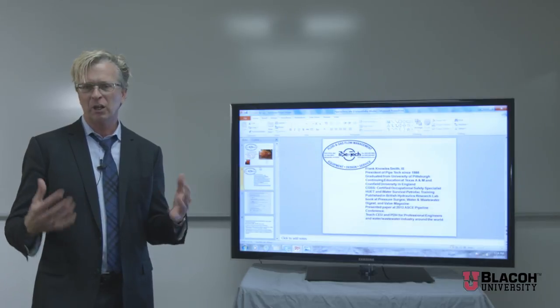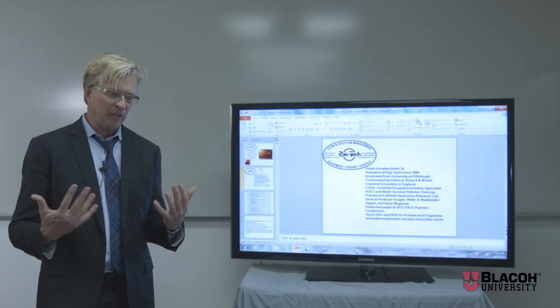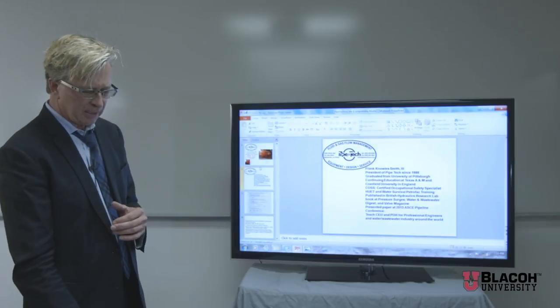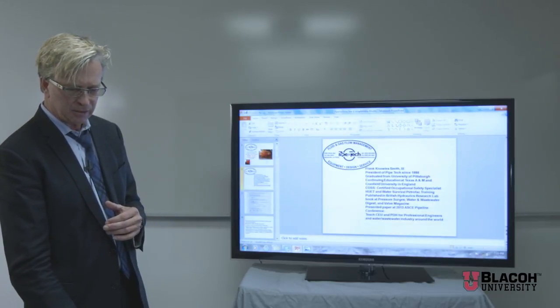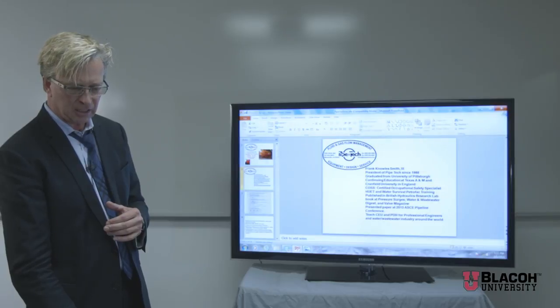We gave the city assurance that their water system would not drop below 15 PSI. We did a proof of design using our transient monitoring equipment that records 100 times a second. On May 27th at 2:15 the pumps tripped and our surge vessel kept the system positive, reacting exactly like our computer surge analysis predicted.